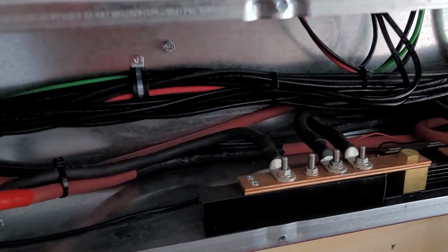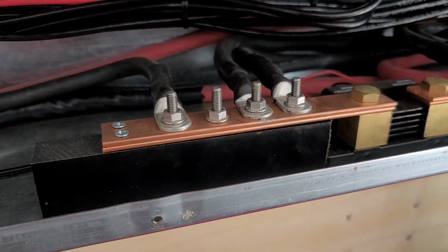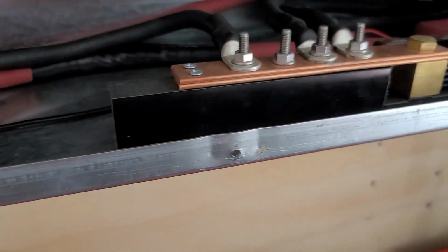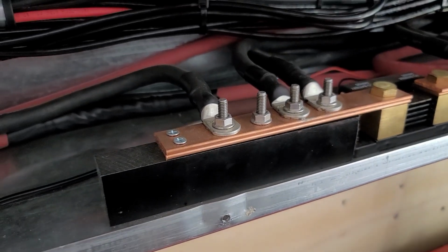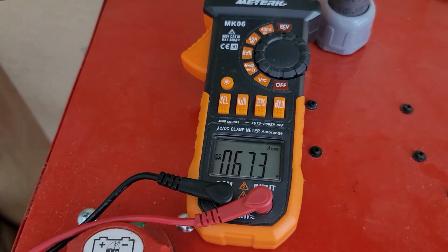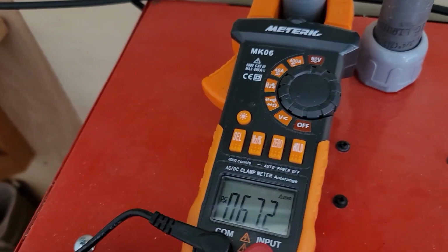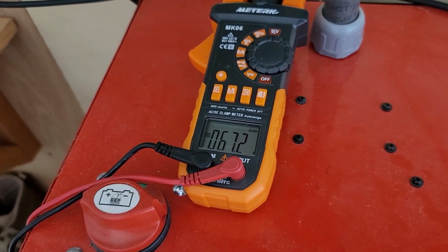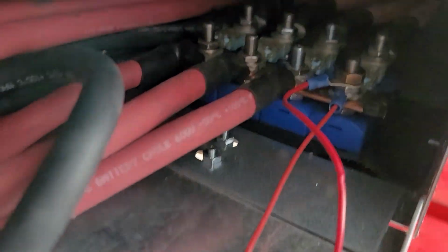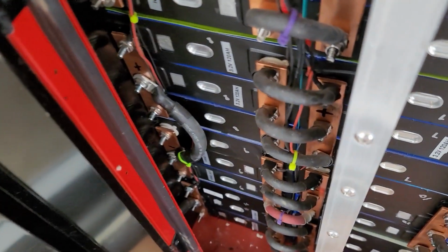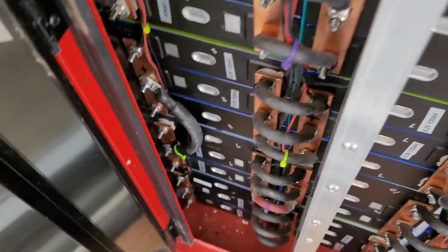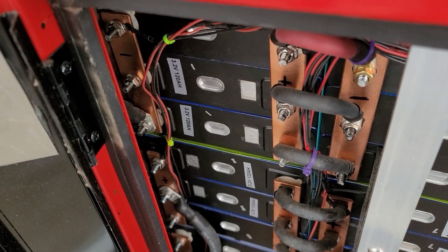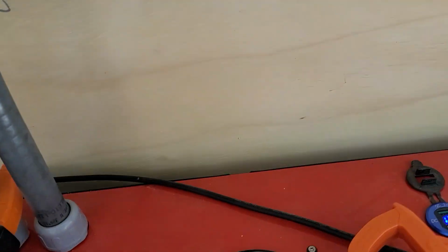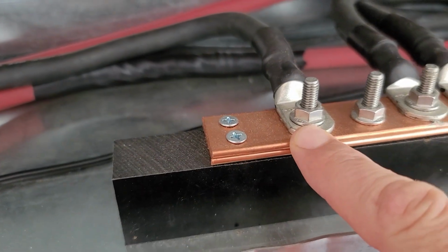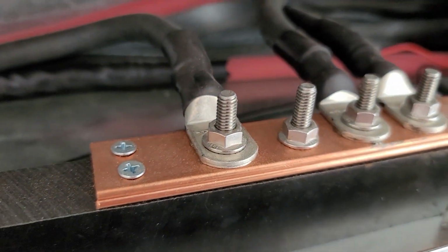It's really difficult to check these numbers again, but I'm going to check them right now and see what we get. That will be off camera, and we will just use that to calculate the total voltage drop across the whole power wall. At 67.3 amps, the voltage drop on the positive side, between the distribution block over here and the positive down on the bottom of the power wall, is 84 millivolts, while the negative on the power wall through the BMS up onto the negative side of this bus bar is 126 millivolts. So we'll use those numbers to calculate stuff later on.